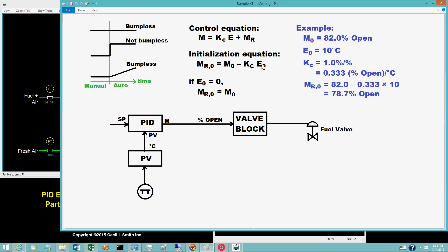For proportional-only control, the controller output bias remains at its initial value m sub r 0. But when the integral mode is in use, the controller output bias is essentially the output of the integral mode and changes whenever the controller error e is non-zero. To achieve bumpless transfer, the value for m sub r 0 only needs to be computed at the instant the controller is switched to auto. Like most commercial digital control systems, the simulator performs these computations whenever the PID block is in manual. If the PID block is in auto, the control calculations are executed; if in manual, the initialization calculations are executed.